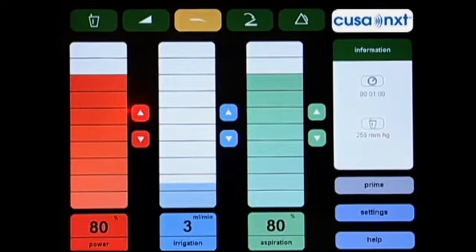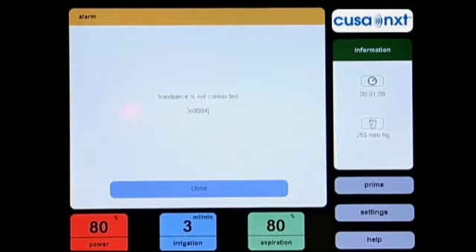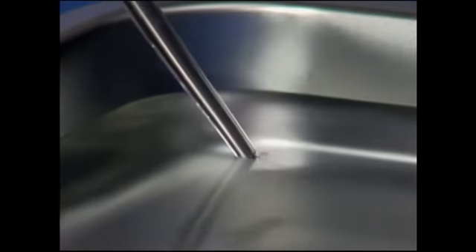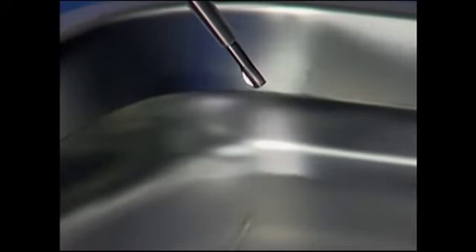To find a resolution to the alarm, press the flashing yellow indicator. Help information will appear on the screen with suggestions for resolving the alarm. It is advisable to occasionally immerse the tip in sterile saline during operative use. This flushes the handpiece, prevents debris from drying on the inner surfaces, and helps minimize the risk of blockage.